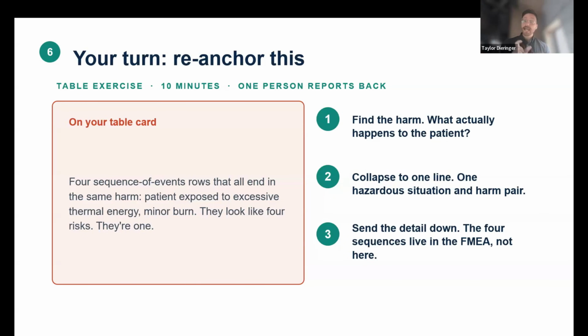Yes, that's great. That's exactly what this hazardous situation-harm pair would be boiled down to: excessive thermal energy, minor burn. Then we can use our hazard categories to identify individual sections of our risk management file that could go into deeper investigation. For example, with thermal energy, there could be a mechanical type, like heat getting trapped, heat sink failure, battery, something where it's a physical interaction, versus some type of software failure that results in a processor being exposed to more work, and therefore more energy being exposed. So it's breaking it down to create individual states of the system that might result in the hazardous situation and harm. But you summarized it perfectly. Patient exposed to excessive thermal energy is the hazardous situation, and the minor burn is the harm.